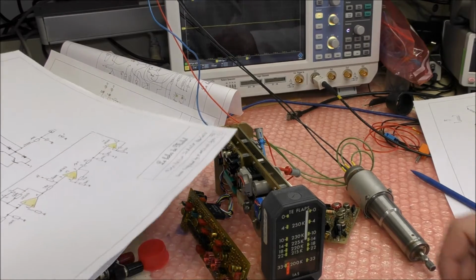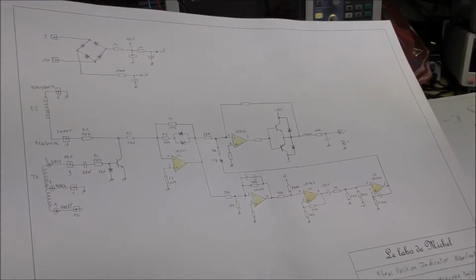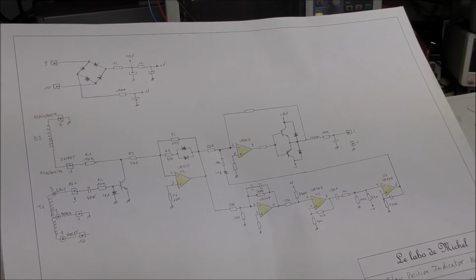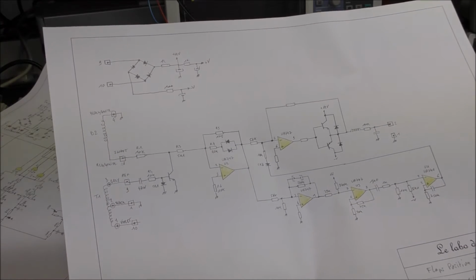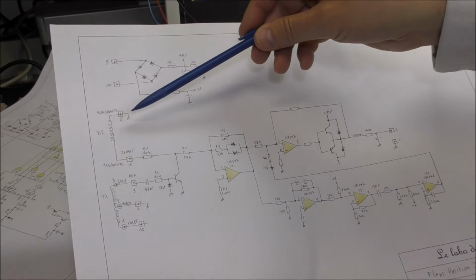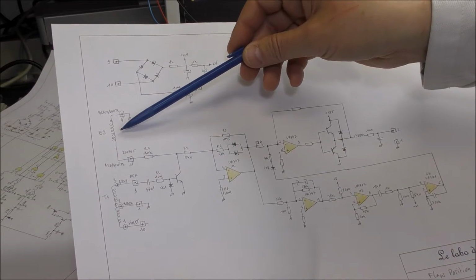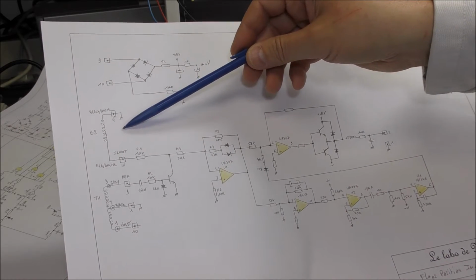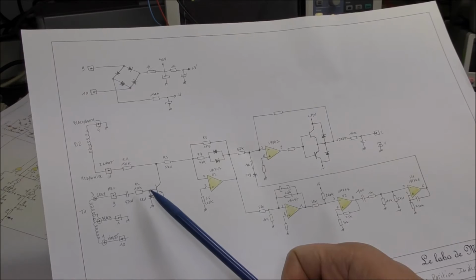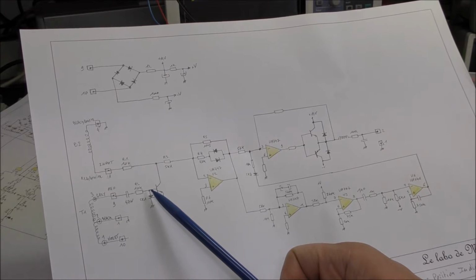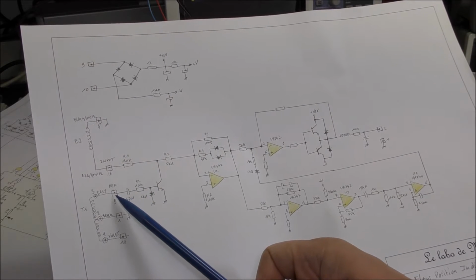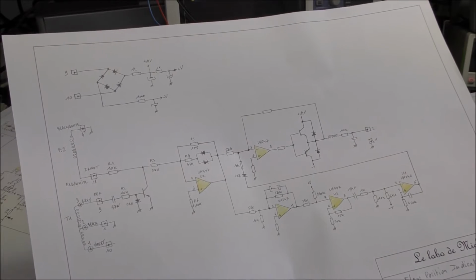This is the schematic of one of the boards which drives the motor. This was explained in my previous video. I have just added the input here, which comes from the rotor of the resolver inside the instrument. The reference signal of the synchronous detector comes from the secondary of this transformer.